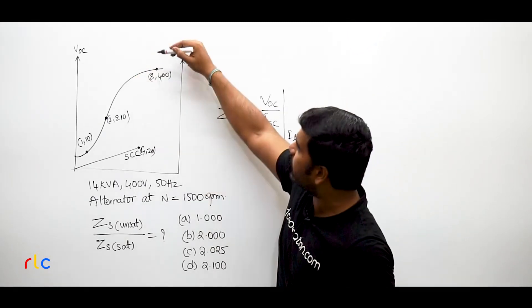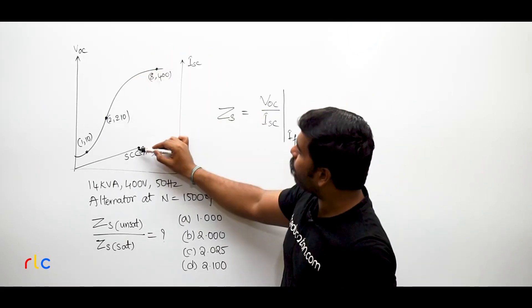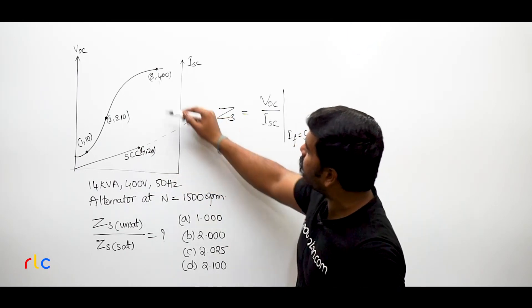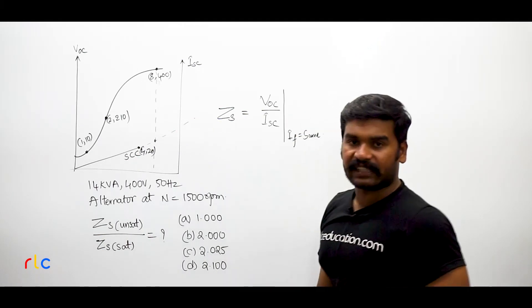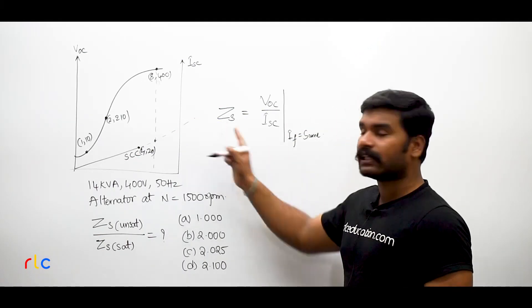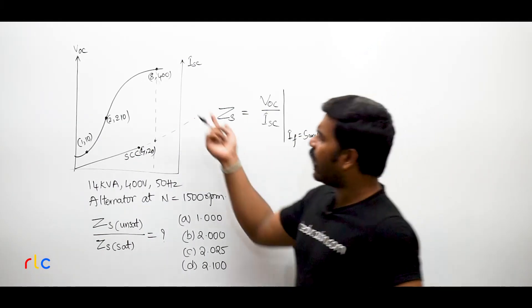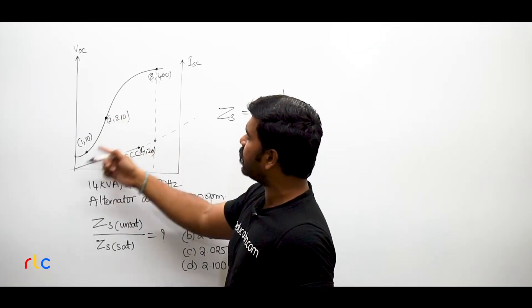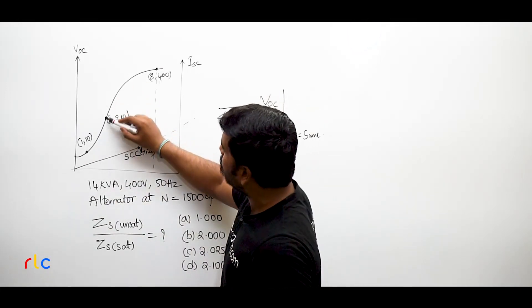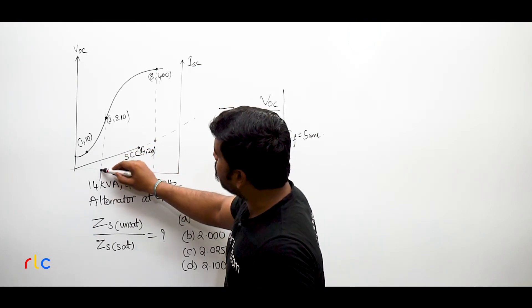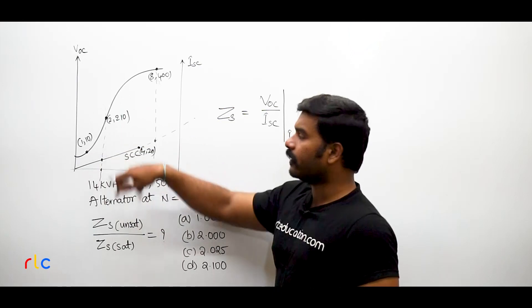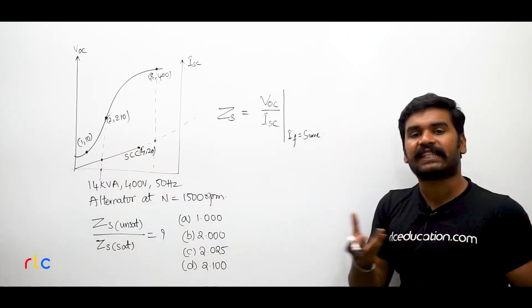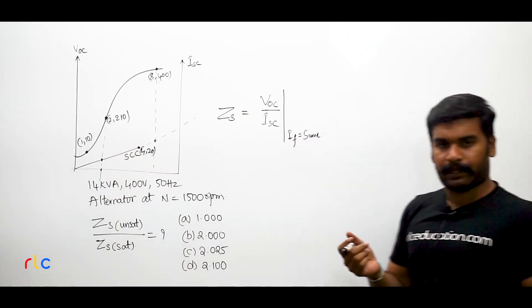So if you are going to take the voltage VOC here and if you are going to extend this SCC characteristic at the same field current here, if you are going to take the ISC, that value of ZS is going to be a saturated one. Otherwise, if you are taking anywhere in between this unsaturated region here, let us say I am taking here VOC and at the same IF I am taking some ISC here, then that ZS is going to be what? My unsaturated synchronous impedance, understood?